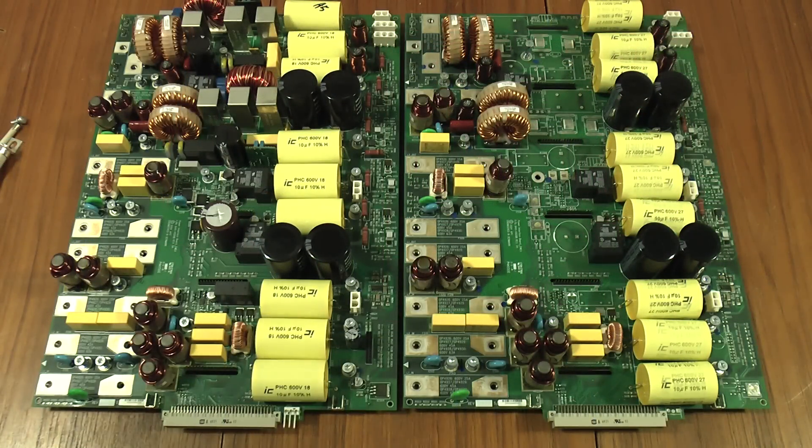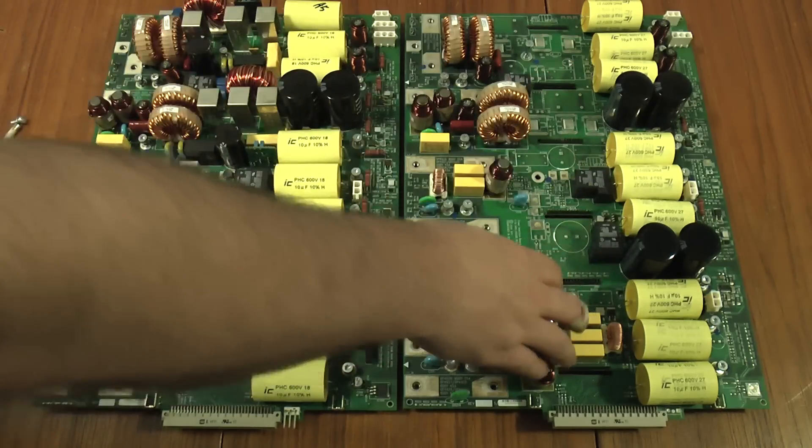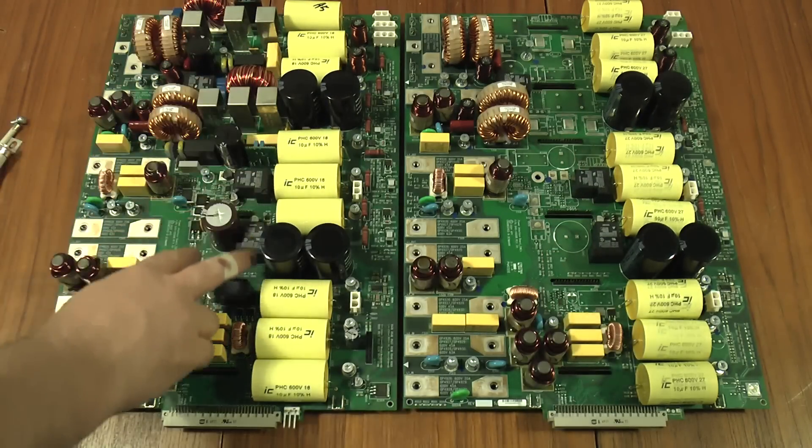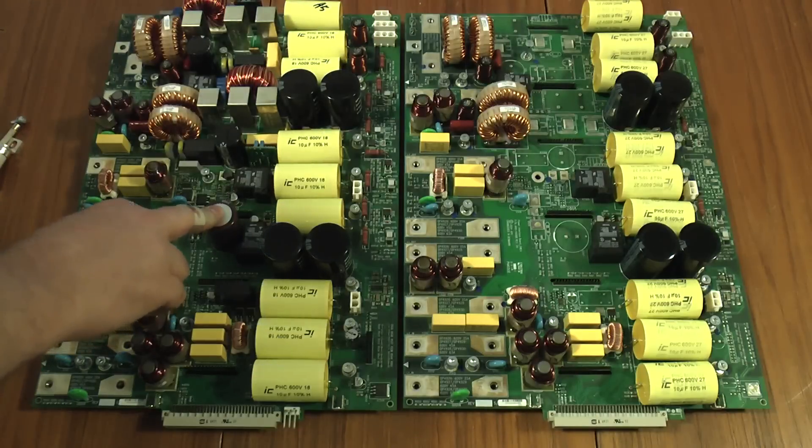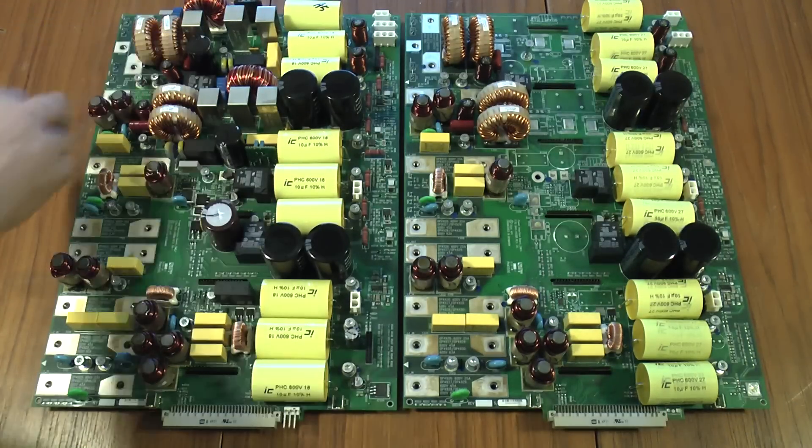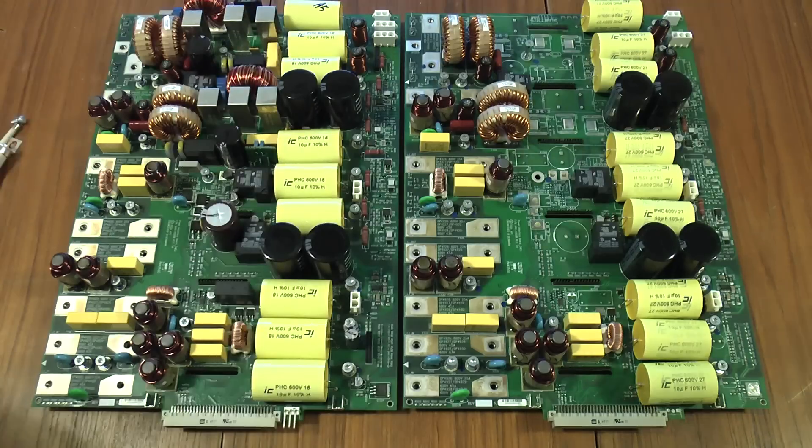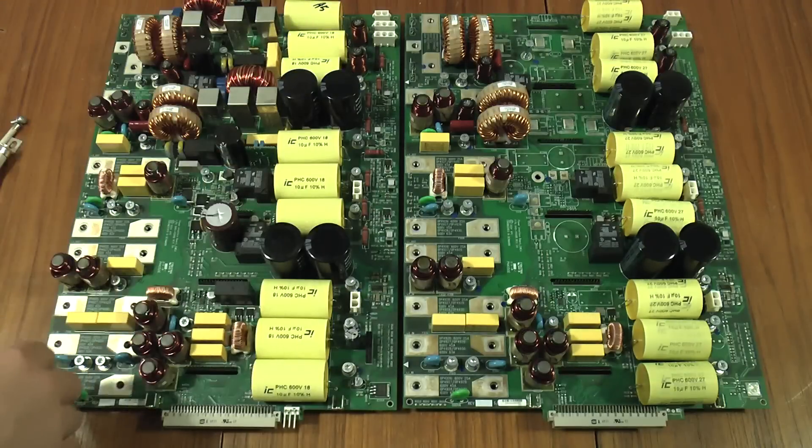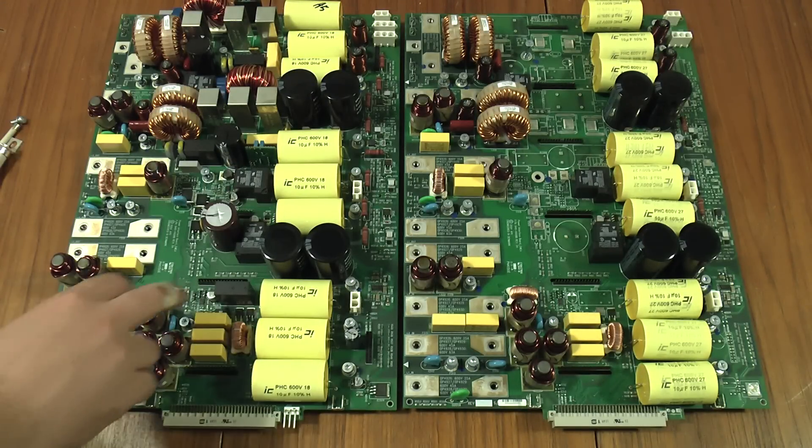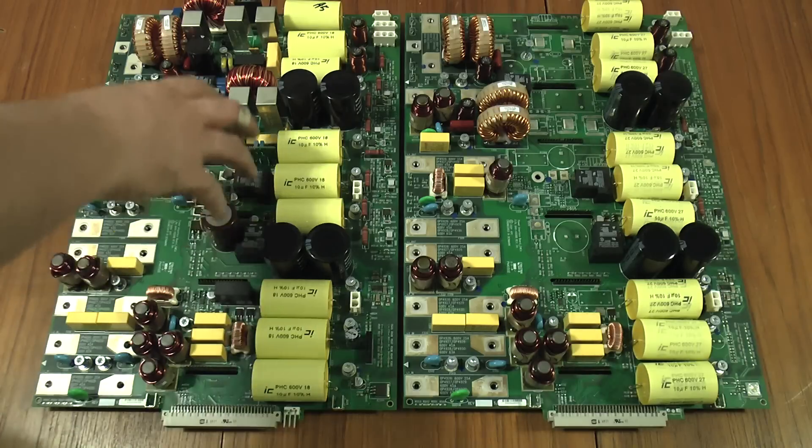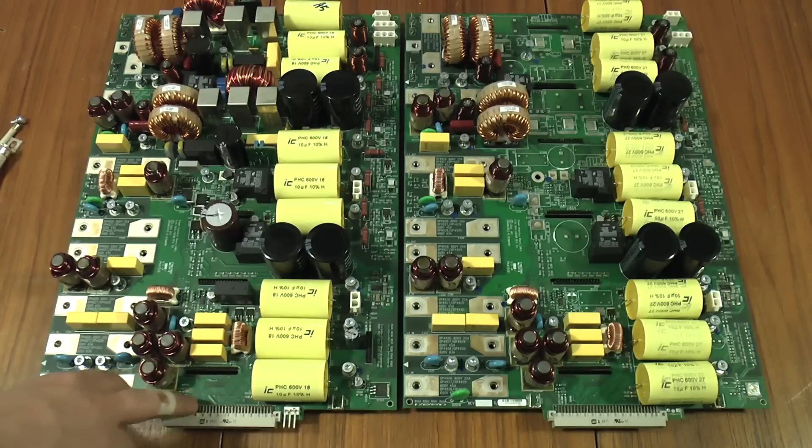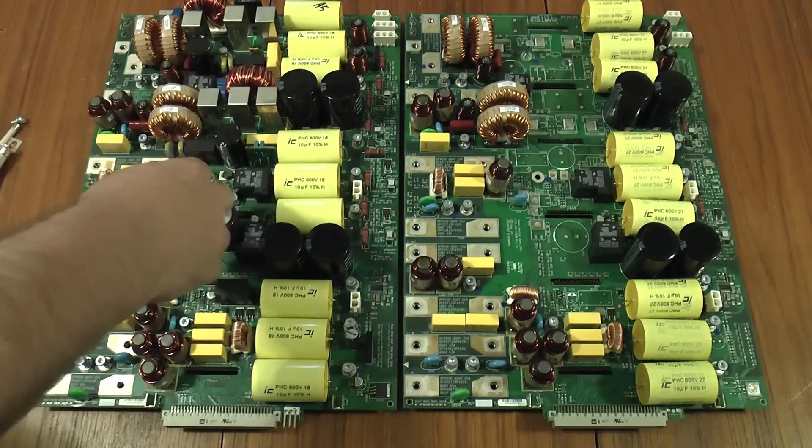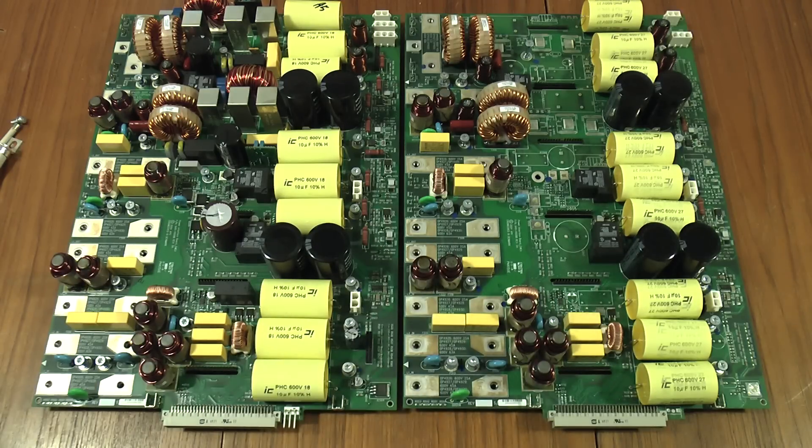Now you can see the difference between the two 20kVA power modules. This is the main one. This is the secondary one that turns it from a 20kVA to a 40kVA unit. And you can see there's a lot more stuff in the middle on this one. That's 400V 220µF. That's 4700µF at 63V. There's another 400V 220 there. Another one of these odd little boards at the top. It looks similar to those little daughter boards on the power modules that sit underneath these. And a few extra relays and bits and pieces as well. Presumably it's only needed once for the whole system. So it may be that whatever these do just go through the back plane into the next board.